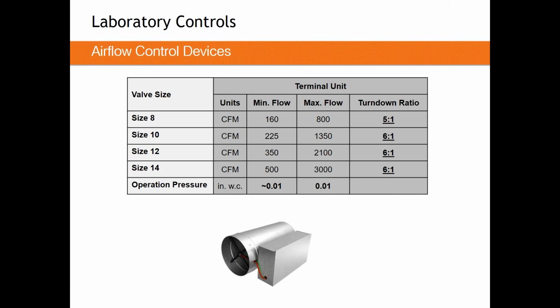If you have that pressure, you'll get airflow through the valve, but you have no control of it whatsoever. If you'd like to control it, you need to damper that airflow off more, meaning you need to increase that pressure drop. So when you look at this performance chart, really there might be one valve or one VAV box in your entire system operating at that minimum pressure. And it's the one as far away from the fan as you can get. Everything else will operate at a higher pressure drop.